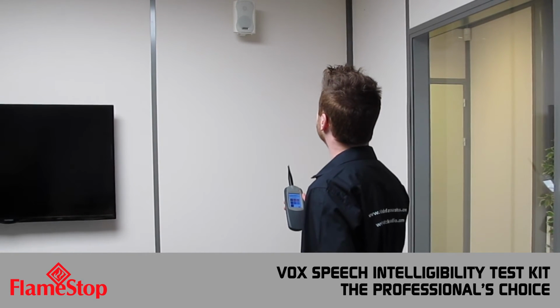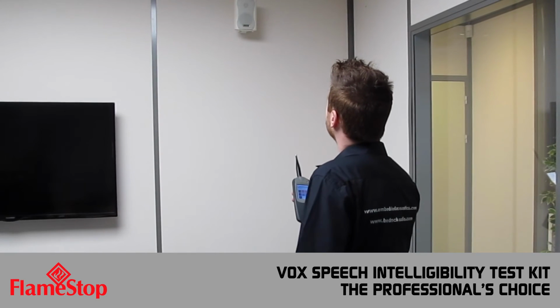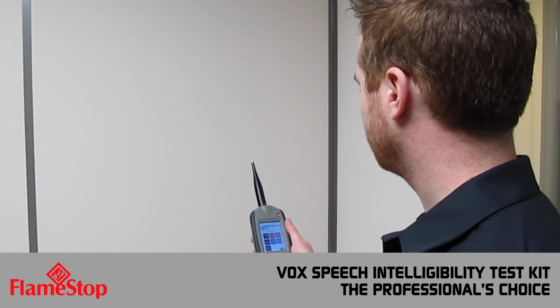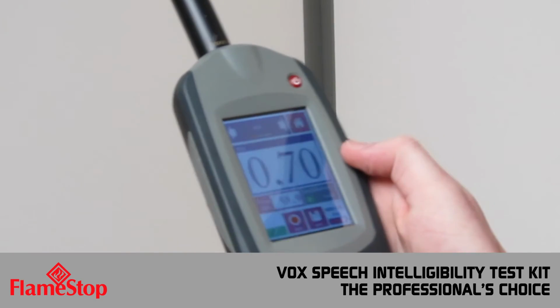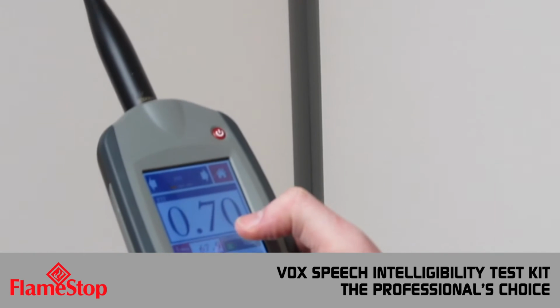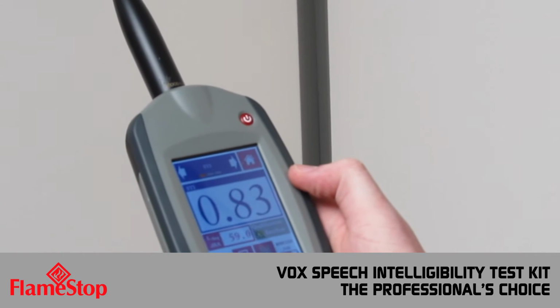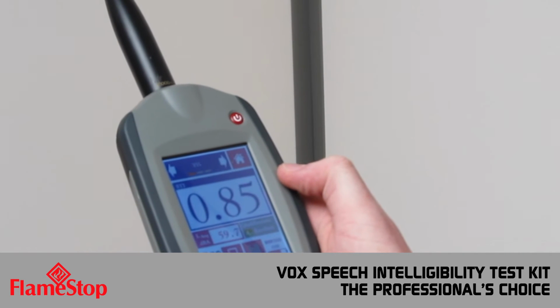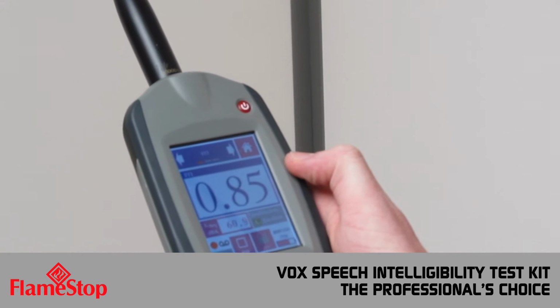The act of performing the STI-PA measurement itself couldn't be simpler. Place the analyzer in the desired position to get tested. You may hold the instrument in your hand, but the most accurate results are obtained when placing the STI-PA analyzer on a tripod stand 1.5 meters off the ground.